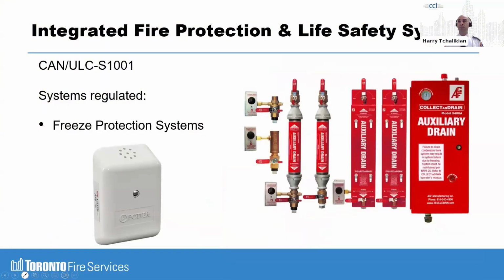Freeze protection systems: if there are thermostats, heaters, drum drip heat tracing, drum drip auxiliary drain boxes in your dry sprinkler system, make sure they're all working and that, as required, they are supervised by the fire alarm system. So you're probably doing 100% of this. Just the one step that you're taking this further is making sure that the heater actually works, that the thermostat freeze protection actually turns on the heater and is also reporting to the fire alarm system.